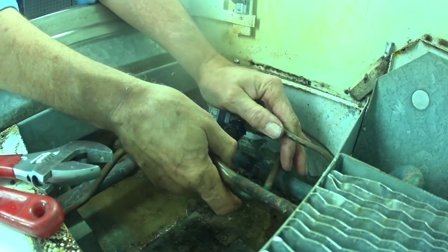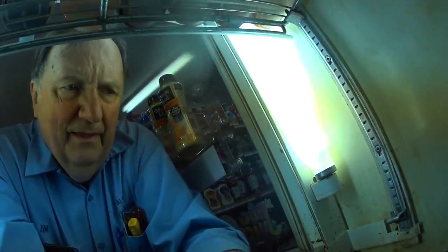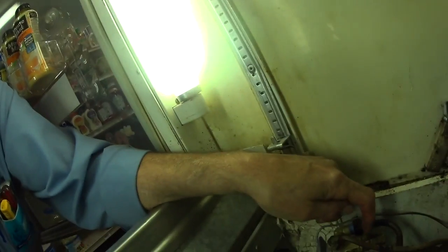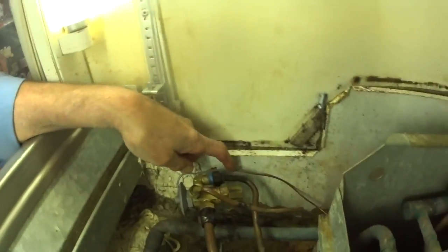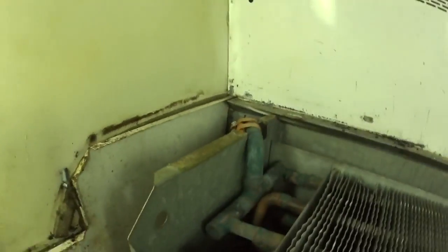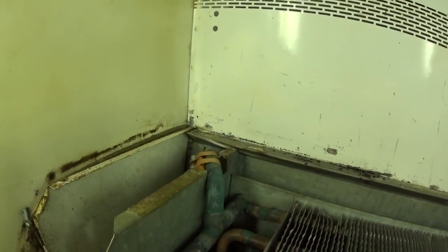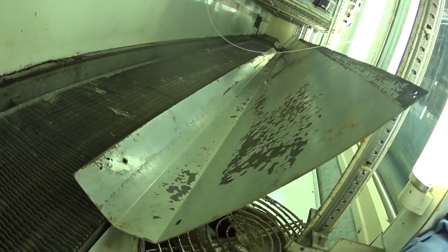Put some soap on it. That's it, guys. We were losing gas out of that every few weeks — about five or six weeks I had to put gas in it. But that was the problem right there. It's always something small. I actually thought it was the tubing, pitted someplace in the middle of the evaporator coil — I took the evaporators apart all the way down. Okay guys, we got that leak fixed. Later.